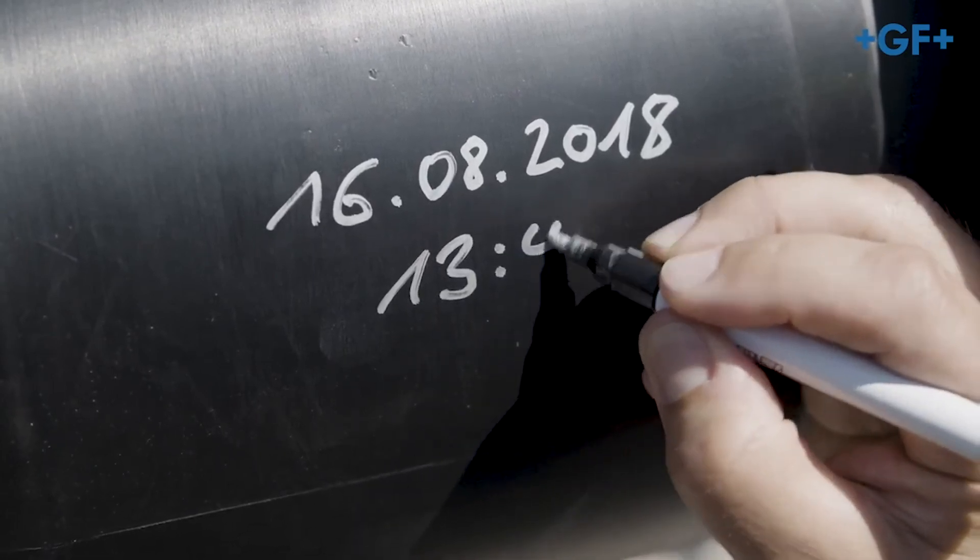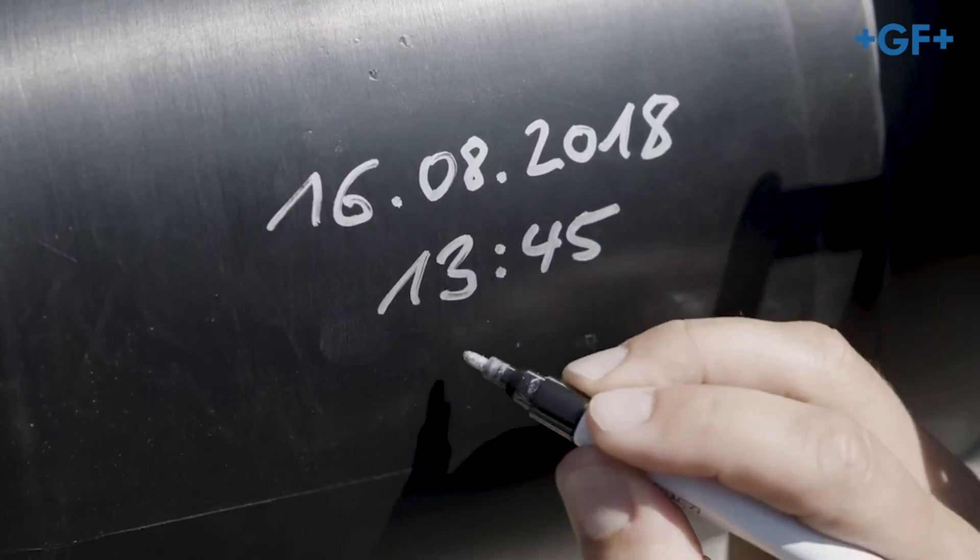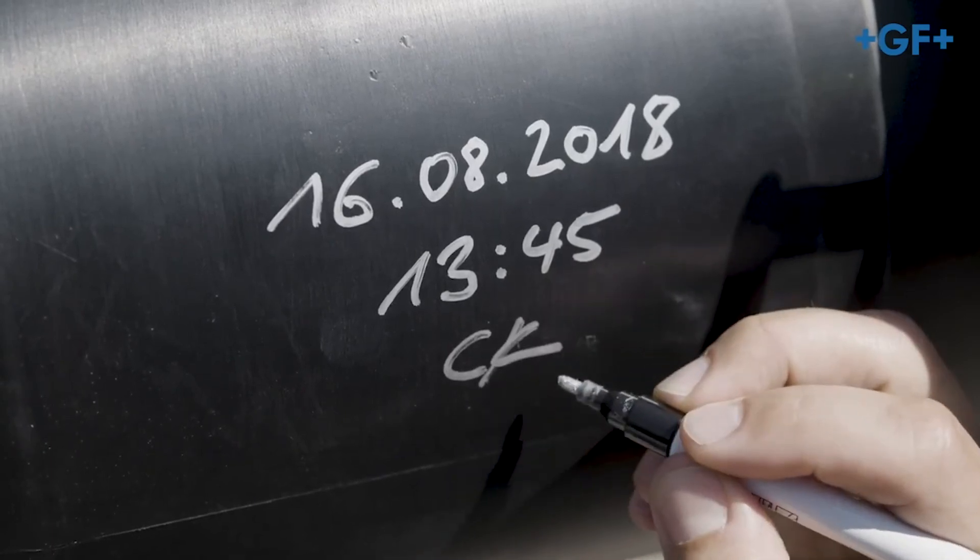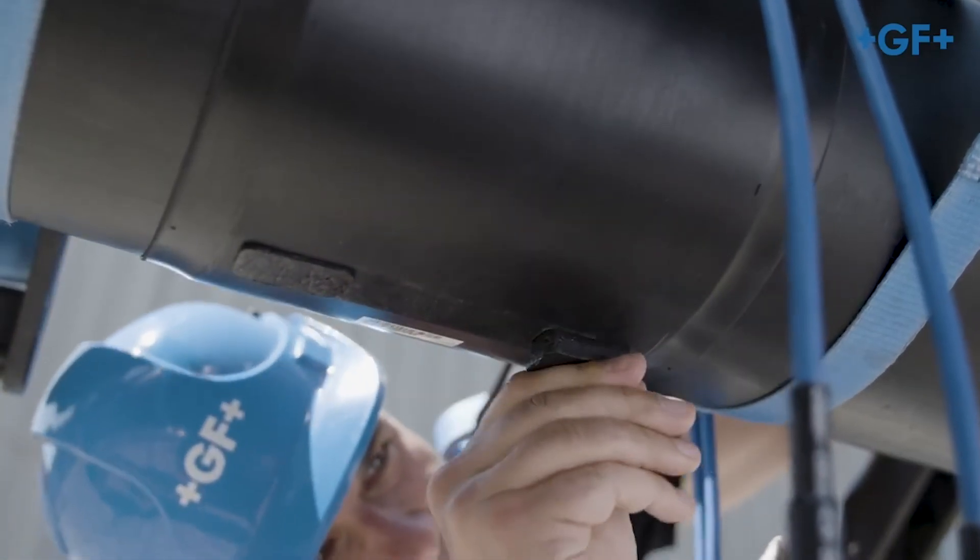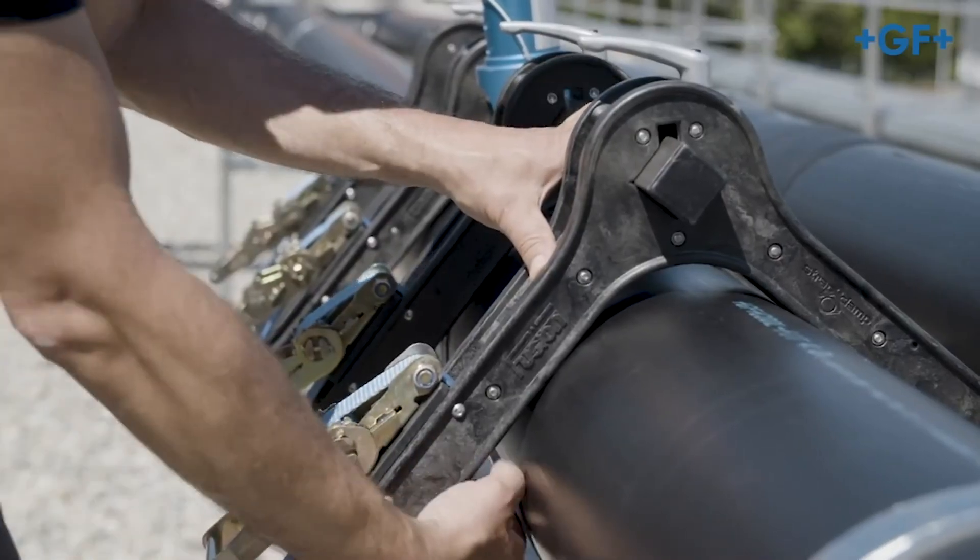Make sure there's no tension and that the position of the fitting does not change before the cooling time has elapsed. Now, place the insulation plugs on the weld contacts. After that, remove the clamp.